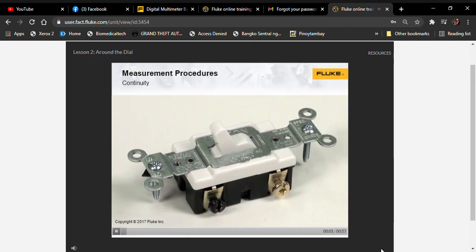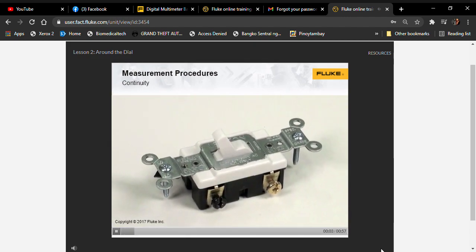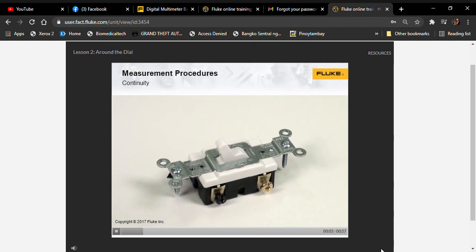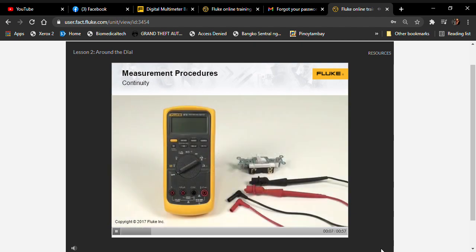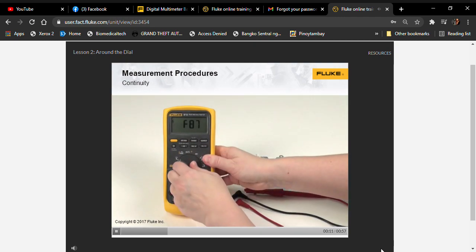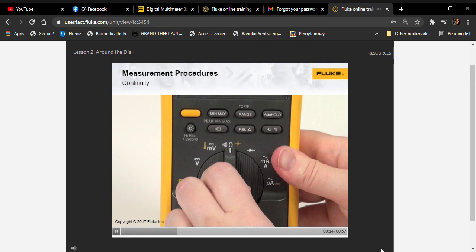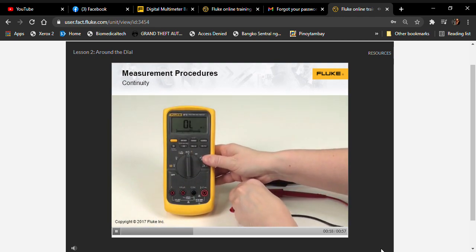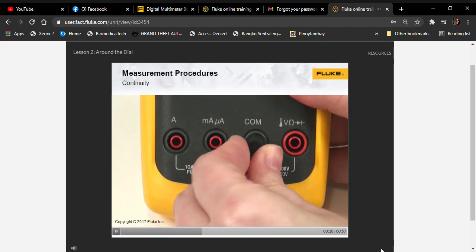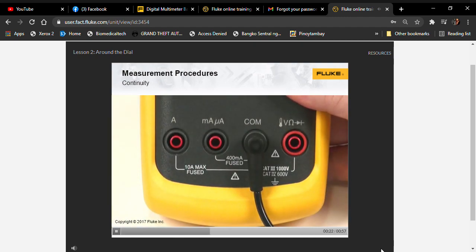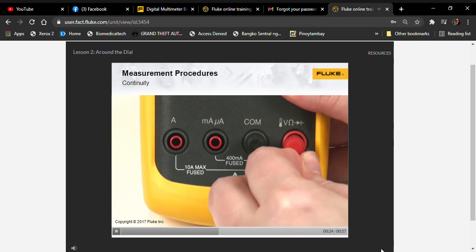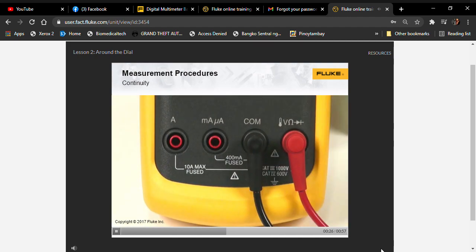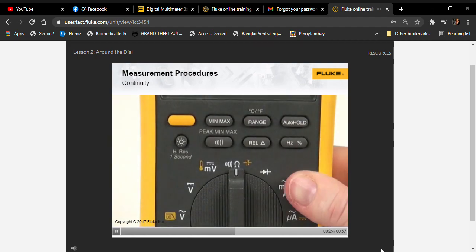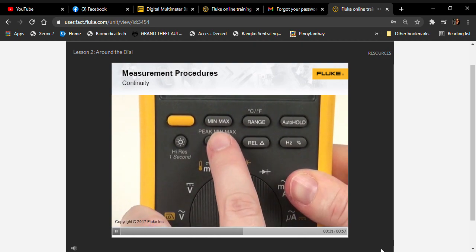When measuring resistance, any component being tested for continuity must be de-energized and removed from the circuit. To configure the multimeter to test continuity, the selector switch is set to the resistance function, indicated by an omega symbol. Then the test leads are plugged into the multimeter's input jacks. The black test lead is plugged into the common jack and the red into the red input jack indicated for resistance. Then the continuity button is pressed to turn on the beep indicator.